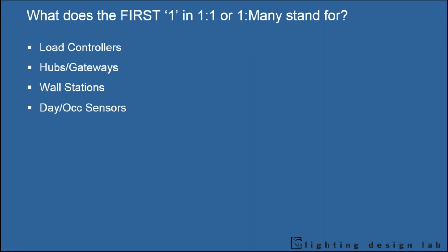So let's bring it out. Hopefully a little bit of a trick question, but I would have accepted two answers here. First answer I would accept is load controllers. In your NLC configuration, you would have one load controller for many fixtures, but just as well, you would also have one daylight occupancy sensor, or a set of motion sensors and daylight sensors, for many fixtures. So those are good answers. Both NLC and LLC configurations will have hubs and gateways at the same rate, that's not going to change. So your load controllers and your daylight occupancy sensors are what designate, hey, if it's one-to-one, that's probably your LLC application.